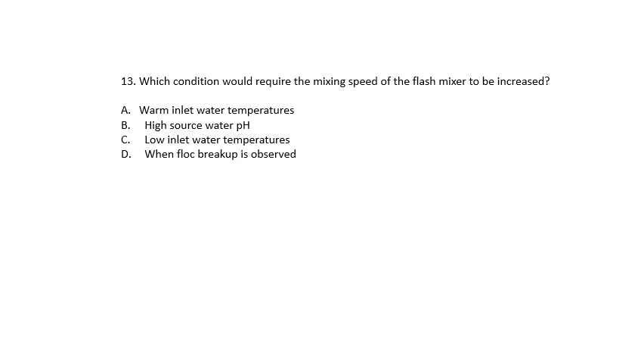Question 13. Which condition would require the mixing speed of the flash mixer to be increased? Warm inlet water temperatures? High source water pH? Low inlet water temperatures? Or when the floc is observed to be breaking up? The answer is C, low inlet water temperatures. The colder the water doesn't react as much, so you gotta mix it more.